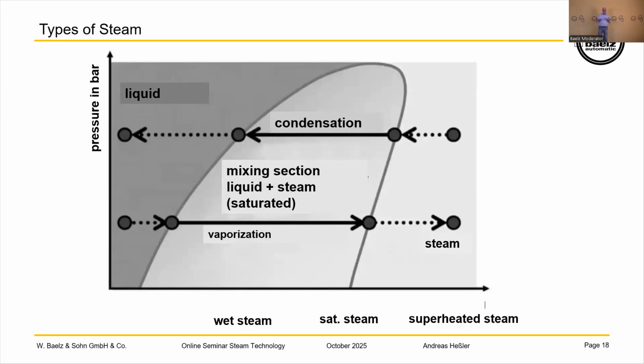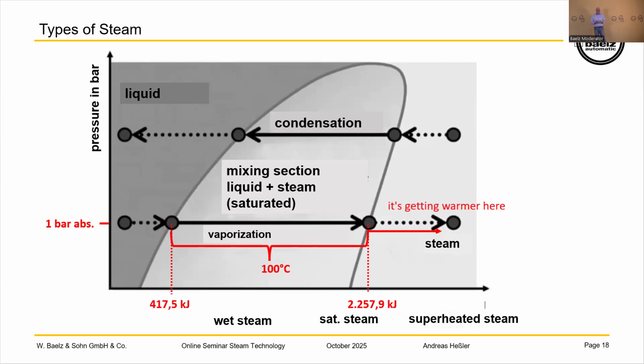Let's see here a steam table to explain how this works together with the liquid and the wet steam. On the left side, you see the liquid. On the right side, you see the steam, and between them you have the wet steam area. For example, we're looking here at 1 bar absolute. We have a saturated steam temperature with 417.5 kilojoule. Then we start vaporizing. That will be at 100 degrees. And after the 100 degrees, we're going from liquid to steam with 2,257 kilojoule. And when you put more heat in there, you will have overheated steam. That looks pretty simple, how it works. And in the other direction, you see on the top, you're going from superheated steam to condensation to liquid.